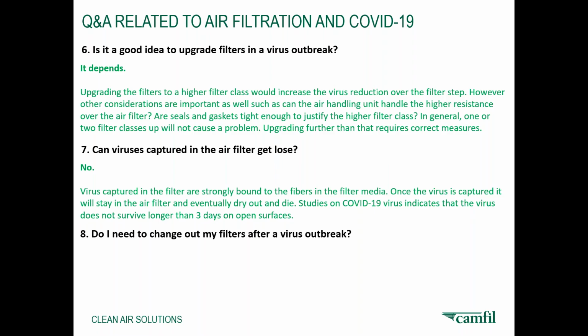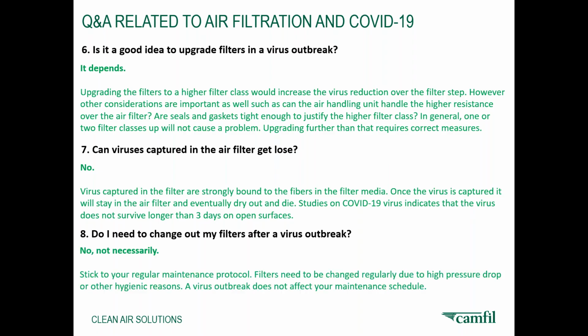Do I need to change out my filters after a virus outbreak? Definitely no. As I said, we need to follow the regular maintenance protocol, and the filter needs to be changed regularly - not because of virus spread or disease, but basically because of the pressure drop, which we need to check. If the pressure drop is high, it definitely needs to be changed.